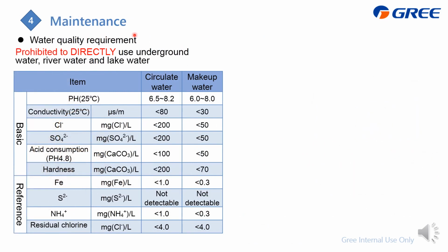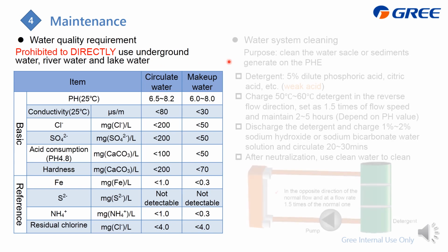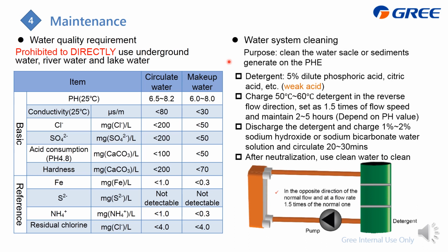Next is the maintenance. As you know, we apply the plate heat exchanger to exchange heat, which requires the water quality to be very high. Due to this, we prohibit directly using underground water, well water, lake water, etc. And here is the detailed requirement of the water quality. Besides, you also need to periodically clean the water system to avoid scale or sediment generation. This is also very similar to the chiller. You can just follow the steps to clean the water system. It's okay.